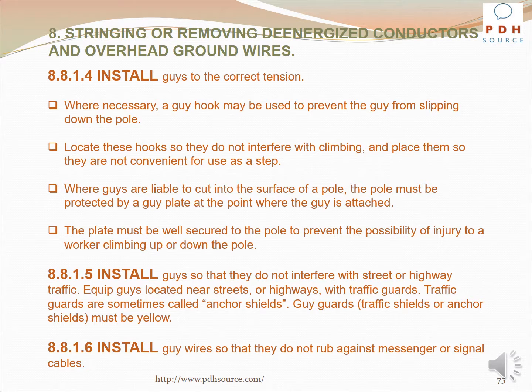Install guys to the correct tension. Where necessary, a guy hook may be used to prevent the guy from slipping down the pole. Locate these hooks so they do not interfere with climbing and place them so they are not convenient for use as a step. Where guys are liable to cut into the surface of a pole, the pole must be protected by a guy plate at the point where the guy is attached. The plate must be well secured to the pole to prevent the possibility of injury to a worker climbing up or down the pole.